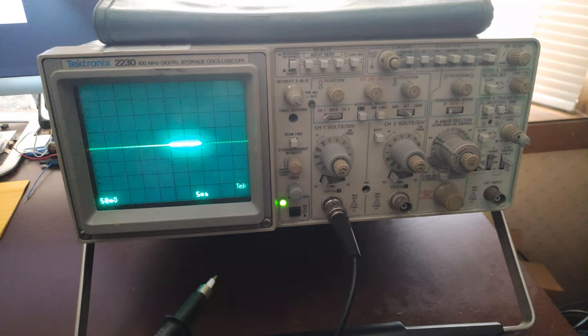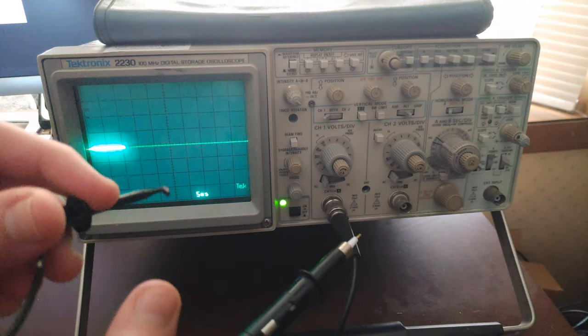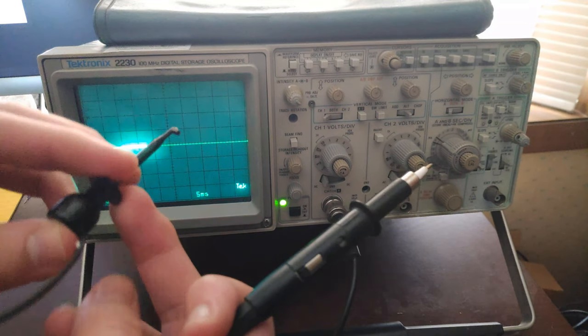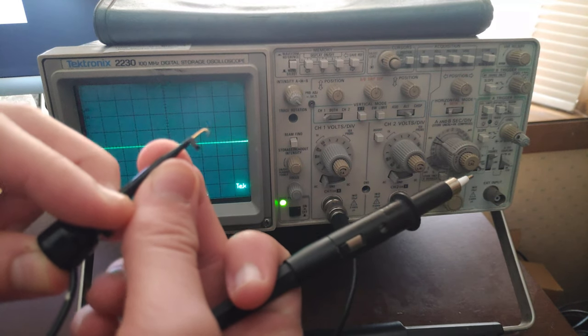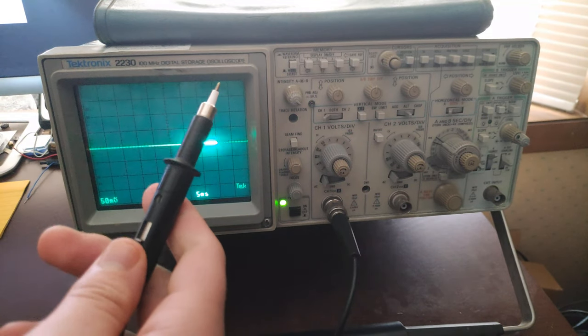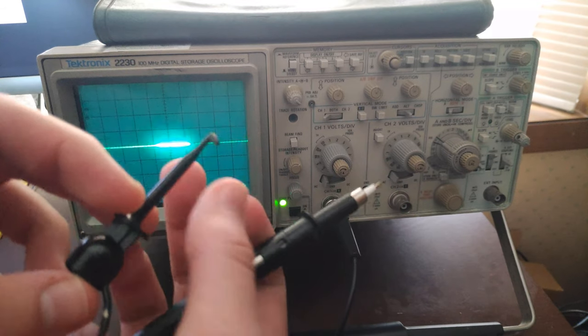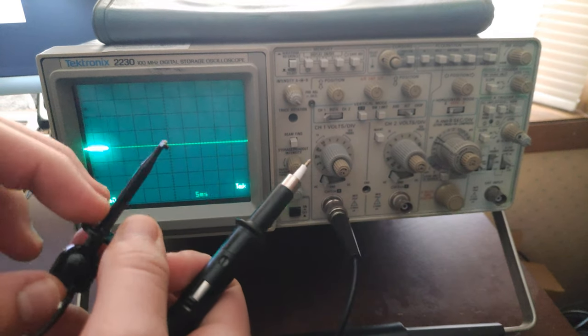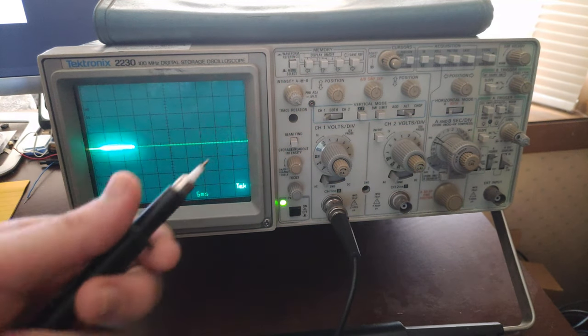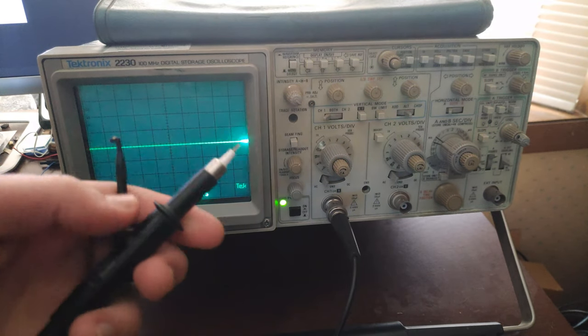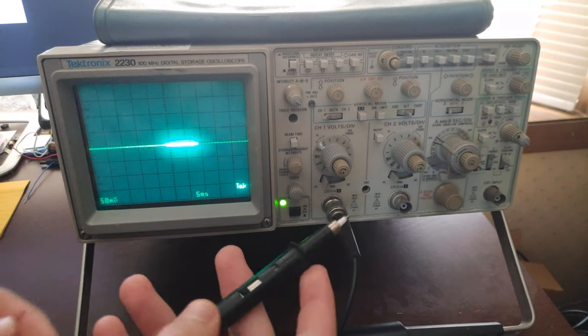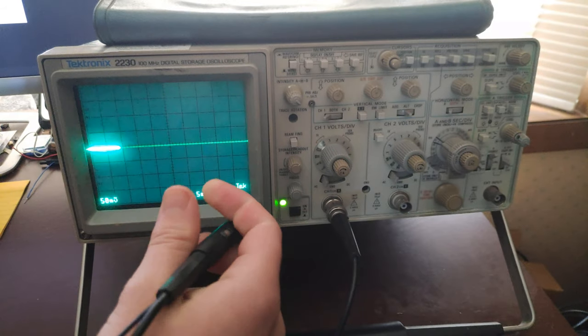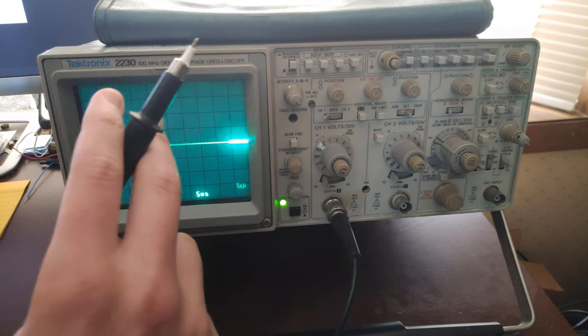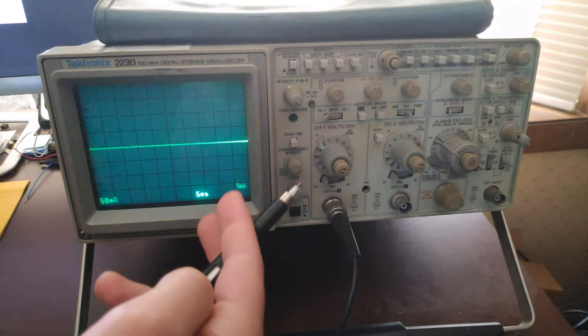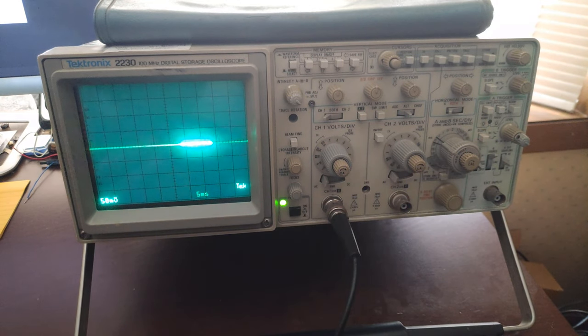And also on the probe, there should be a ground connector. Now this one has a little hook on it to hook to ground, but you might have an alligator clip or something else. So anyway, you're going to want to hook that to ground, obviously, and this is where you're going to hook to your circuit, wherever you want to look on your circuit.